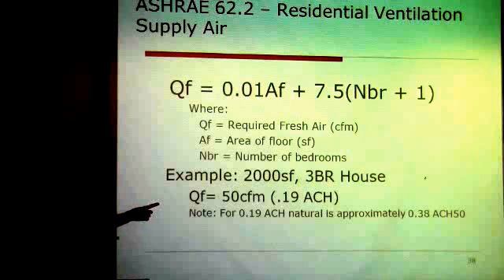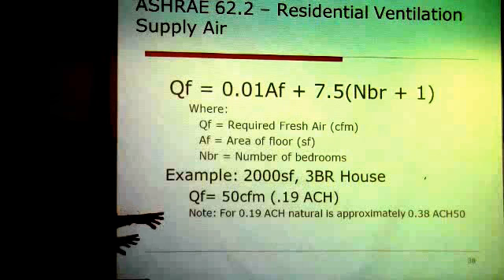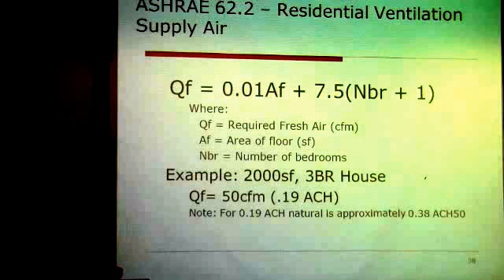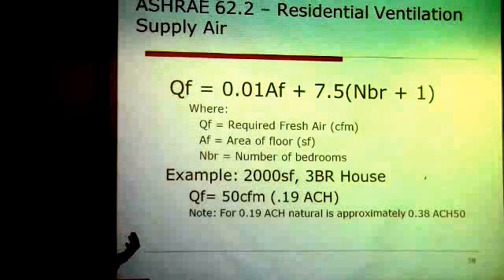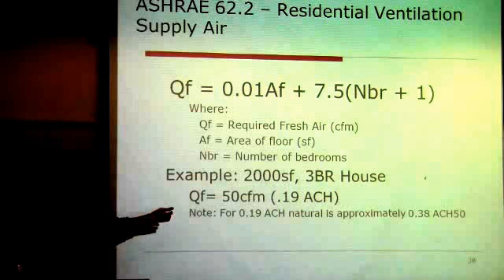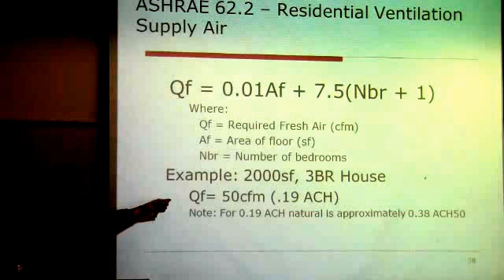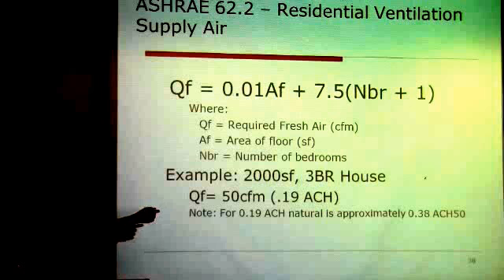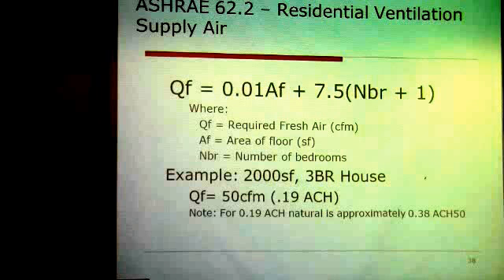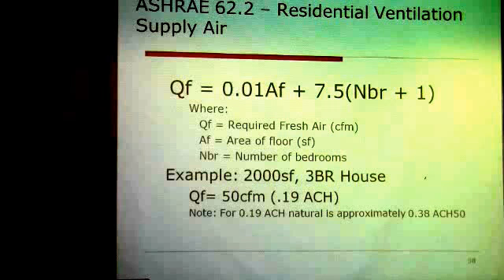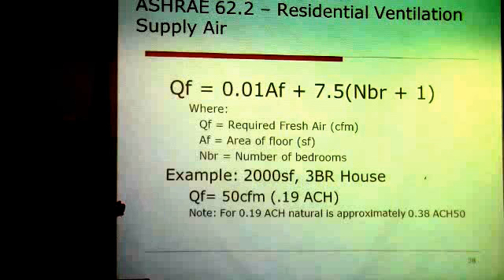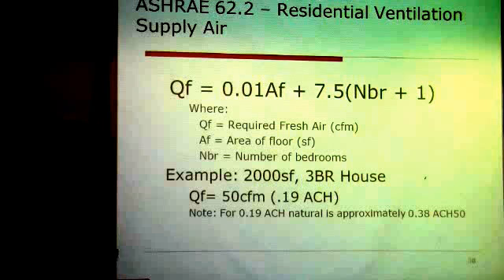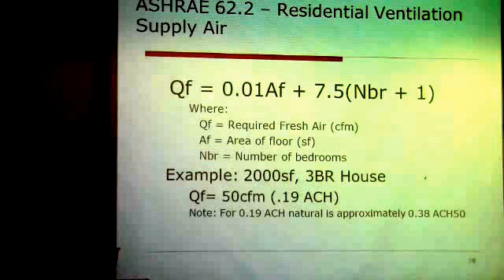0.19 times 20, 3.8. So that's my typo. Excuse me on that. So it's just saying if you have a house that's less than 4 air changes per hour at 50, you start getting less than the required amount of natural ventilation. So most houses in the past have been above 5 air changes per hour. You didn't have to really worry. But once you get below 4, you can't really rely on natural ventilation giving you the required amount.